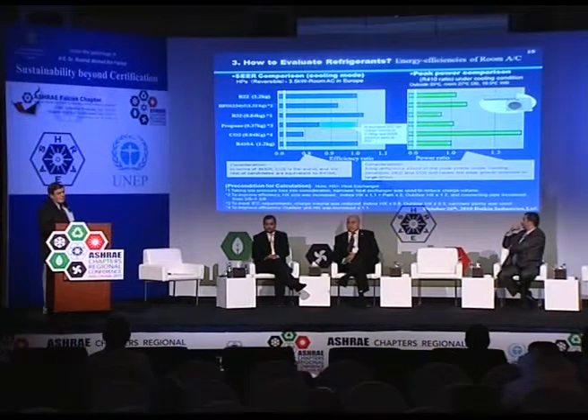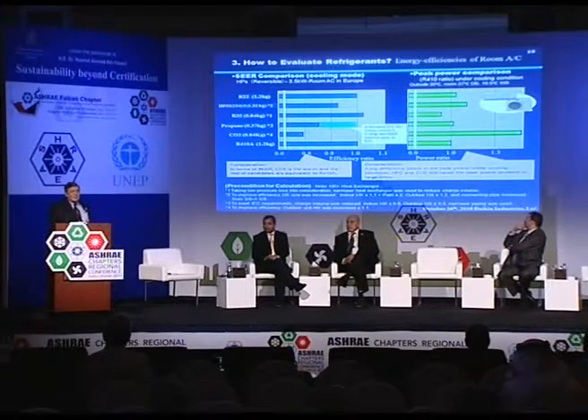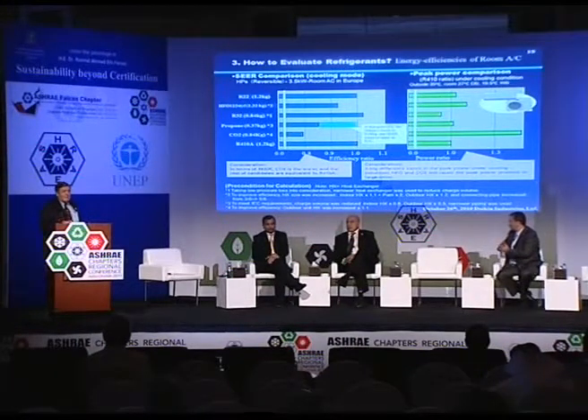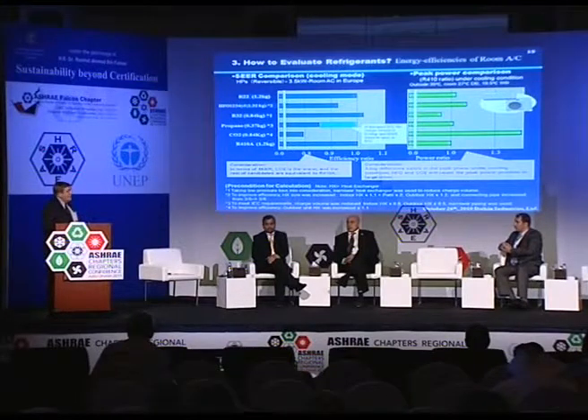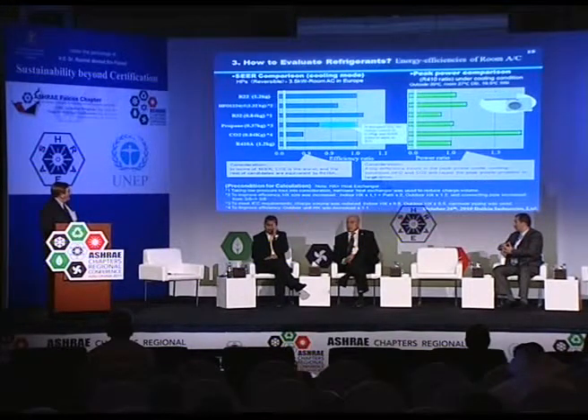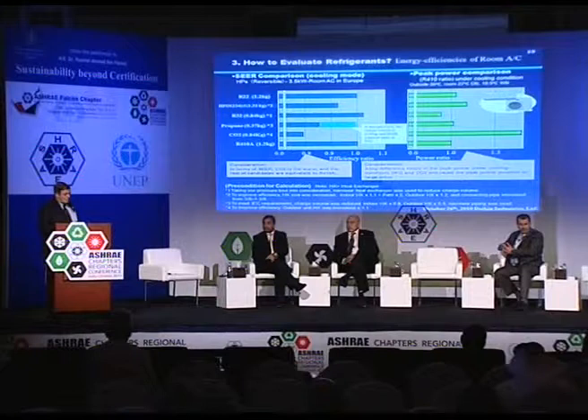Peak power should be a big concern in this part of the world, since it reflects a hot day in Abu Dhabi at 46 or 50 degrees C. You're putting stress on the grids and want to minimize that. On peak power, everybody's about the same except CO2 again, which presents a major problem. So the use of CO2 is starting to fade away, whereas we can still look at R32 and the HFOs as possible substitutes.